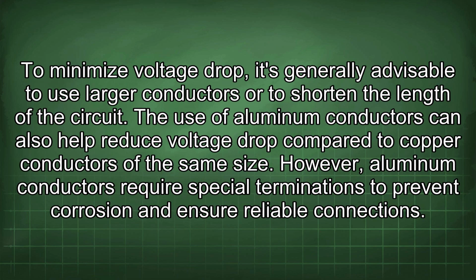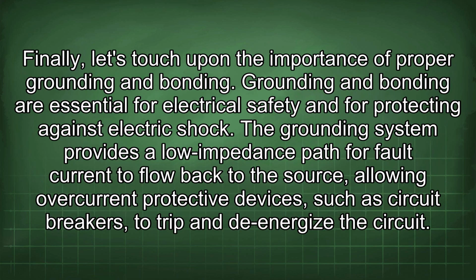To minimize voltage drop, it's generally advisable to use larger conductors or to shorten the length of the circuit. The use of aluminum conductors can also help reduce voltage drop compared to copper conductors of the same size. However, aluminum conductors require special terminations to prevent corrosion and ensure reliable connections. Finally, let's touch upon the importance of proper grounding and bonding.